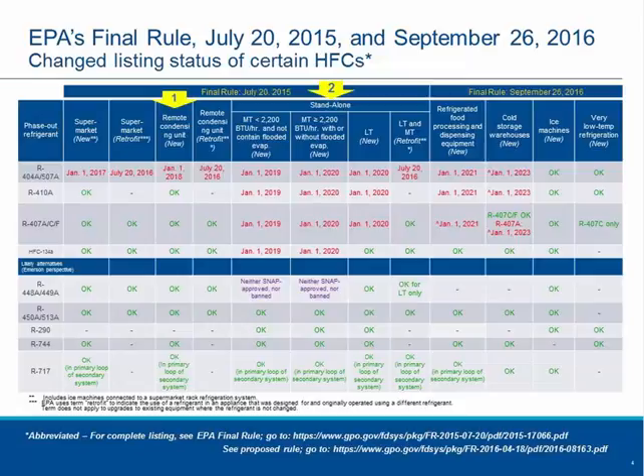These are typically field charged, and they typically will be applied for walk-in coolers and freezers, or sometimes even commercial refrigeration equipment, where the condensing unit is located either outside of the service area or in the back of the house. So for that, this is a big deal with 404A being delisted. In addition, arrow number two that you see is for standalone. These are factory charged systems that get shipped out into the field, so they're leaving the equipment manufacturers already with the refrigerant. And there you can see that R404A as well as 134A is being delisted starting in January 2019 as well as January 2020, depending upon whether the medium temp is less than or greater than 2200 BTU an hour.